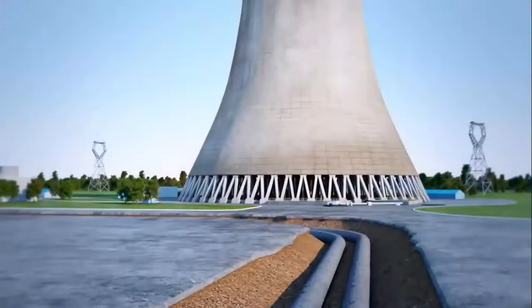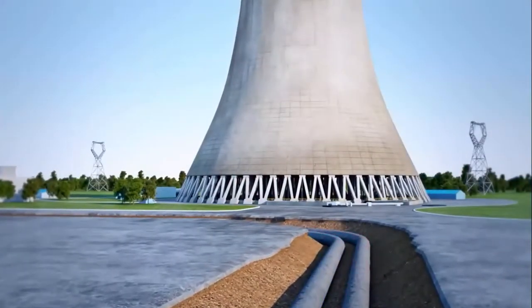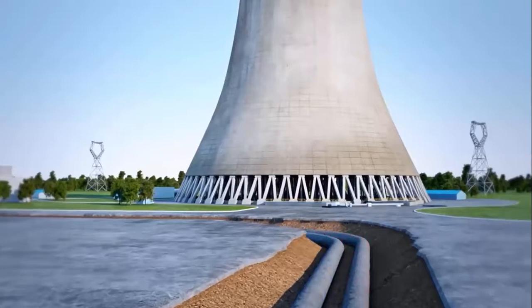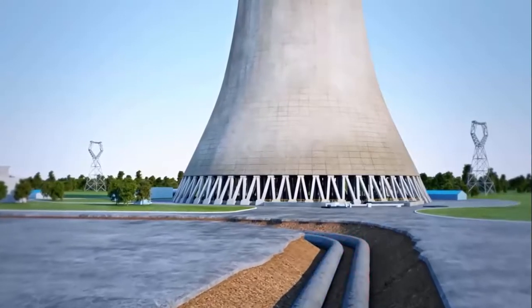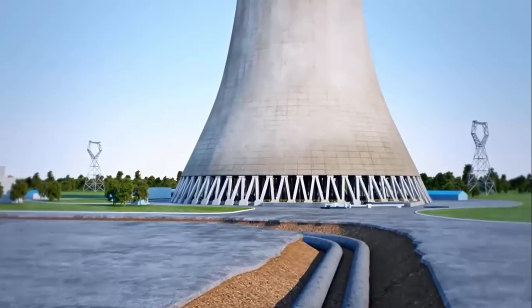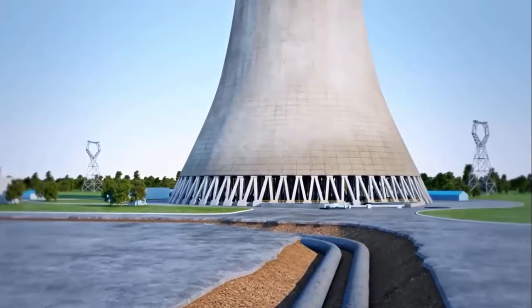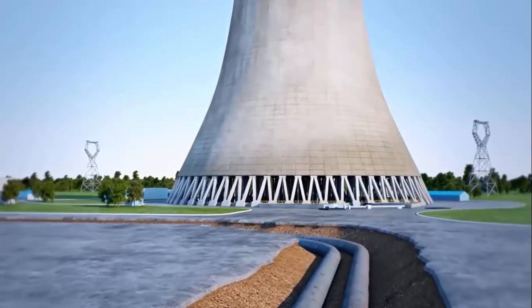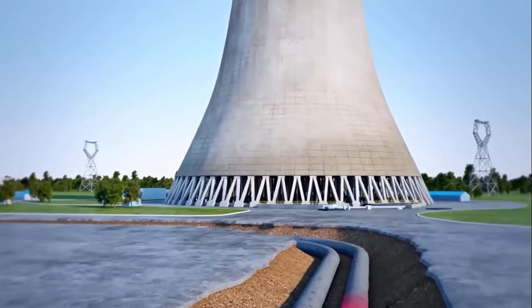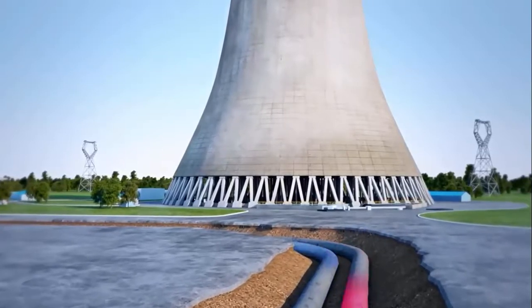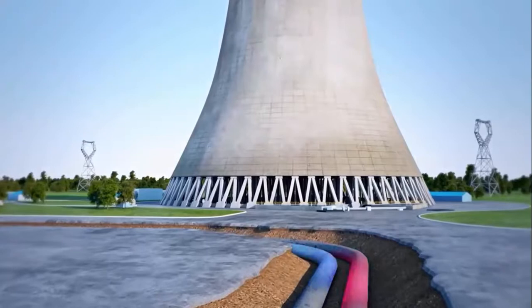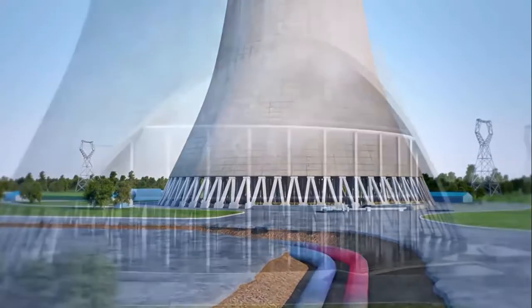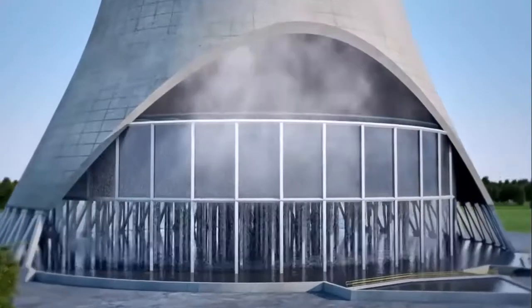Let's take a closer look at the circulating water the plant uses, starting at the cooling tower. Cool water is pumped from the cooling tower basin through large pipes to the condenser to absorb most of the heat from the turbine exhaust steam, leaving us with warmer water that must be cooled. So the warmer water is circulated back to the cooling tower, where it enters through riser lines to the top of the cooling tower fill.